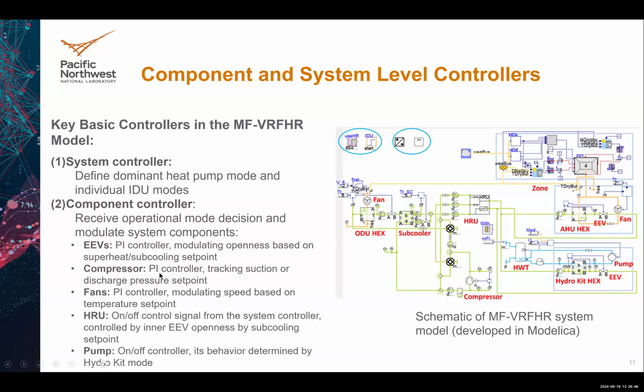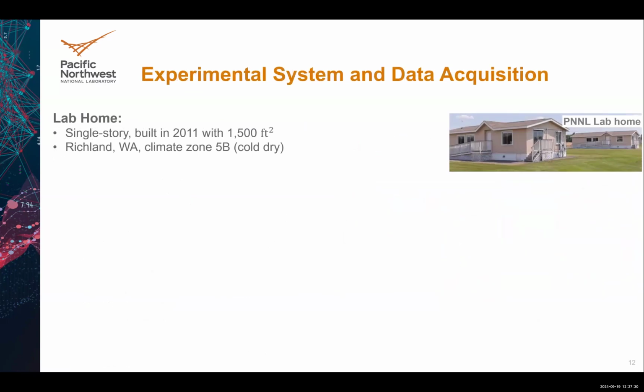For the compressor, we still use a PI controller to track the suction or discharge pressure set point. We also have fans, like indoor fans and outdoor fans. These fans modulate speed based on the temperature set point. Another two components are the HRU and the pump. Those are controlled by on-off controllers. So they will receive the operation mode signal from the main controller based on different operation modes. So this is how we control this entire system. When we have the model and controller ready, in the next step I will show our experiment system in a real building and how we collect the data.